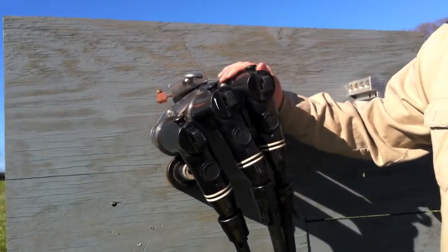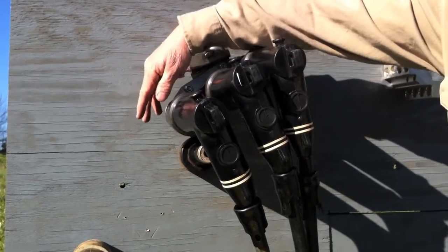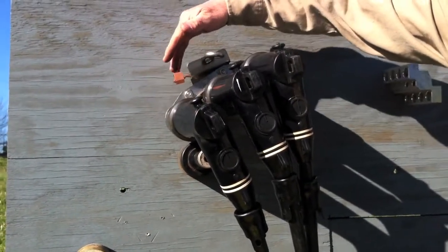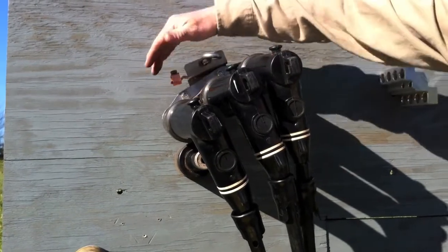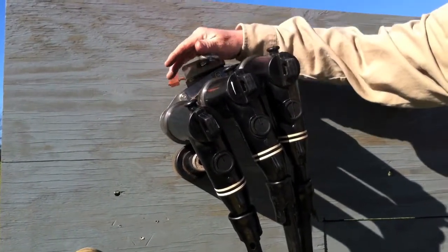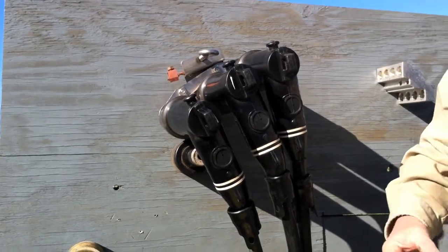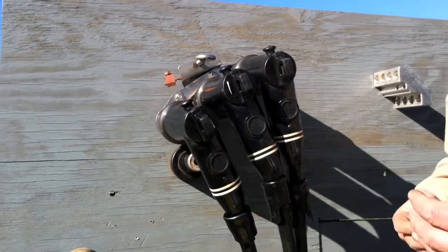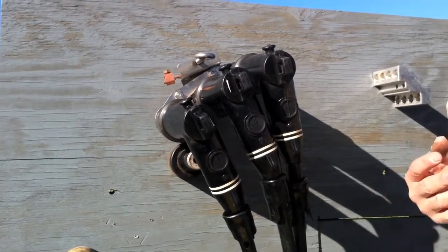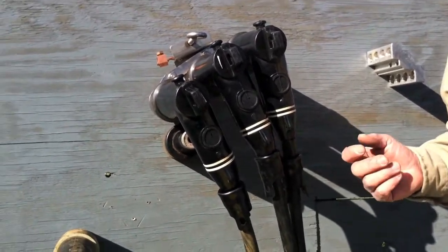Another great feature to this is with the feed in, feed out, all your external loads come through here. But internally, when you're feeding through the transformer under max load conditions, you're building up amperage, which is adding heat to the transformer, which can make the transformer go out. It's the heat buildup that can make them explode.